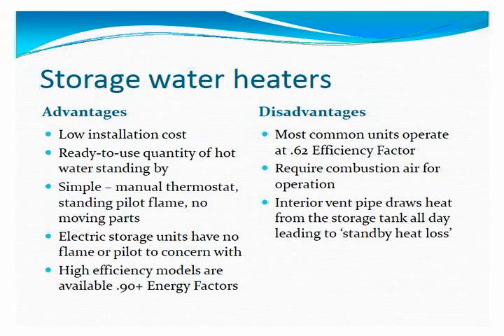Electric storage units have no flame, no pilot light, nothing like that to be concerned with, never a possibility of carbon monoxide poisoning, which is always a potential with any gas-fired appliance. Gas models can have high efficiency at 90% or higher. Electric units are always 90% or higher that we're aware of. Some disadvantages though, the most common efficiency factor is about 62%, 0.62 efficiency factor, meaning quite a percentage of your heat energy is going right up that exhaust flue pipe and little going to hot water itself.